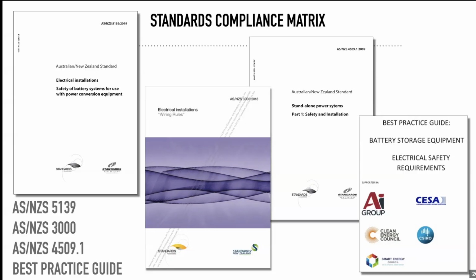Jonathan, I think you're trying to just pop in a few random ones there, but look, yes, New Zealand and I think either Slovenia or the Czech Republic are the only 2 countries in the world that meter in this strange way, which is in a 3-phase installation. They meter each phase independently and they don't aggregate them in real time. So if you're exporting on one phase, you get one rate for the power, and importing on the other phases, you get another rate. They don't aggregate the 3. So it is a real issue for New Zealand and Slovenia and or Czechoslovakia that you have a design that considers that strange method of metering. So that's an explanation of standards compliance.